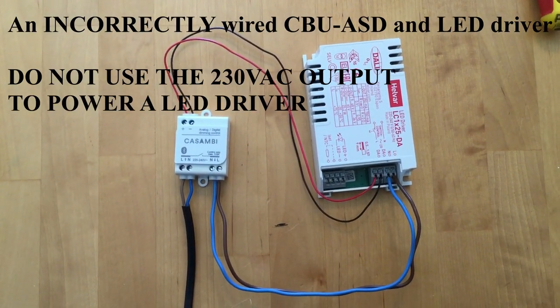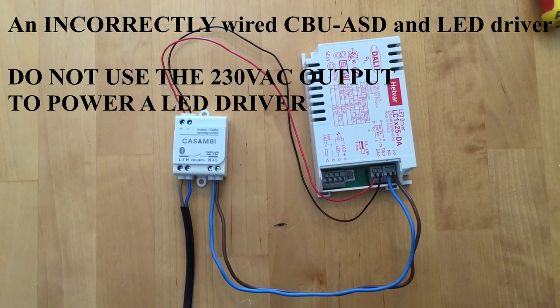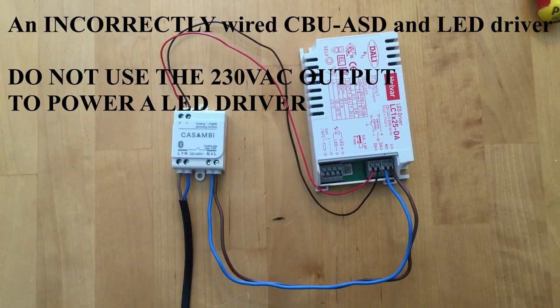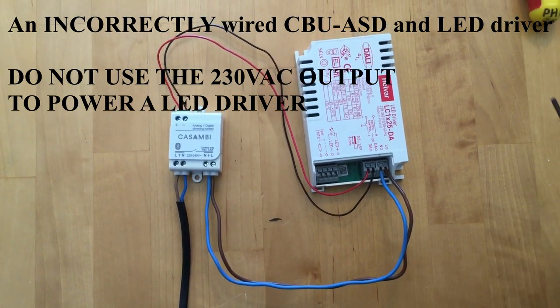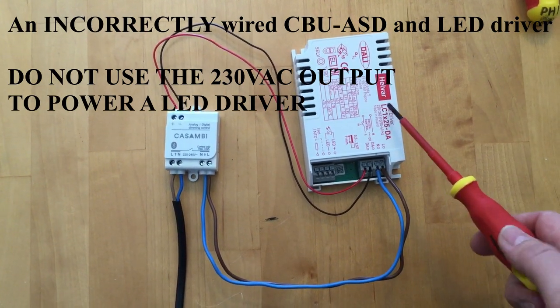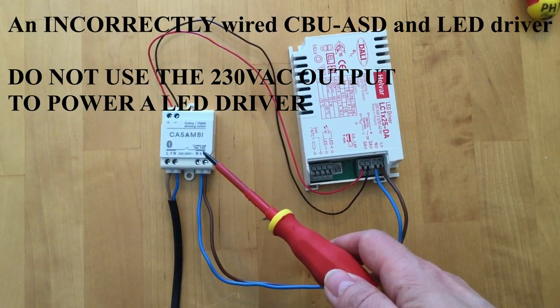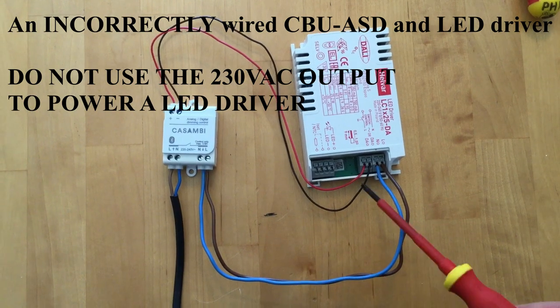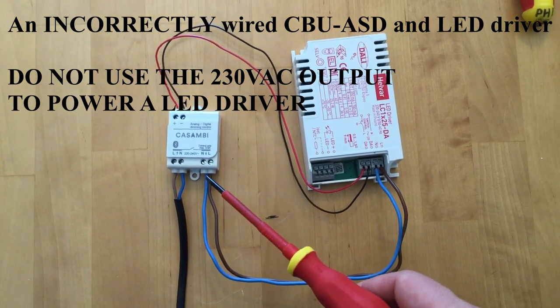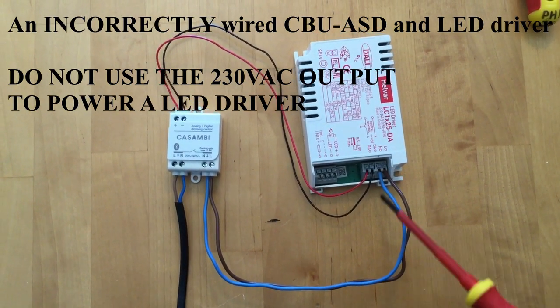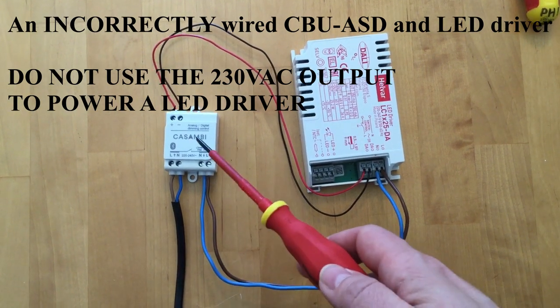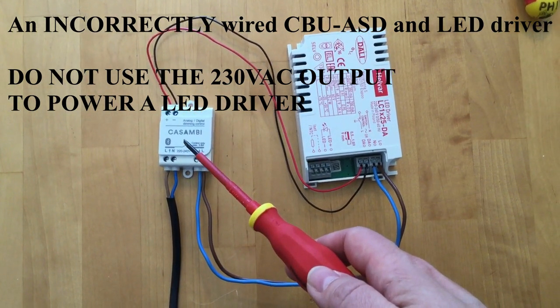This shows an example of an LED driver and a Casambi ASD which have been incorrectly wired. The LED driver is taking its power directly from the ASD, which it should not do. If this was to be powered on, it would eventually damage the ASD.